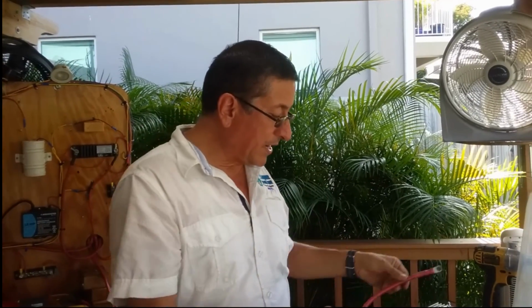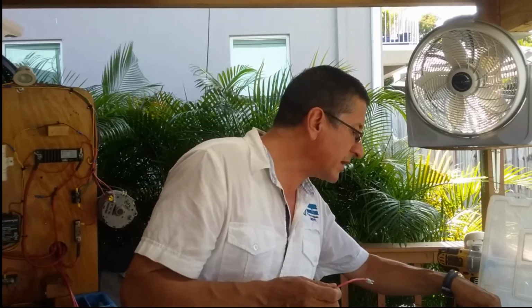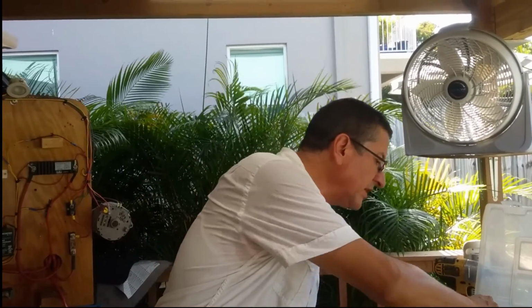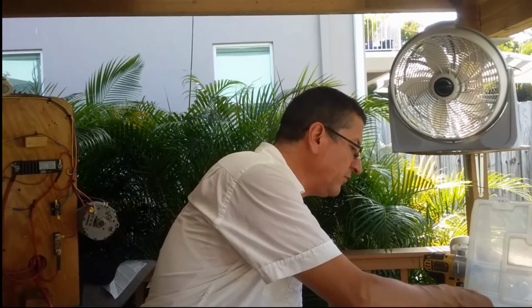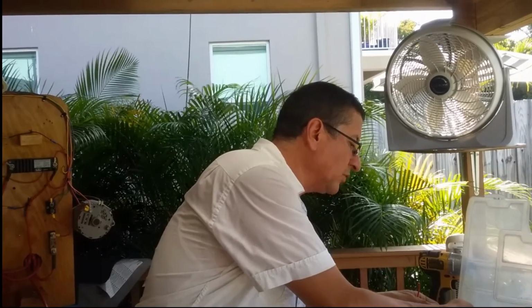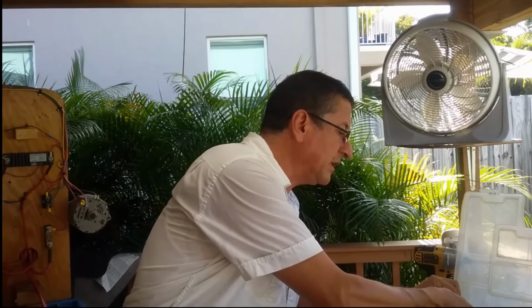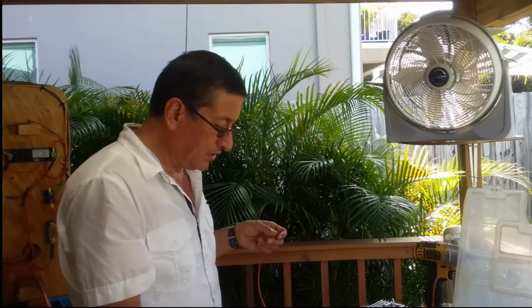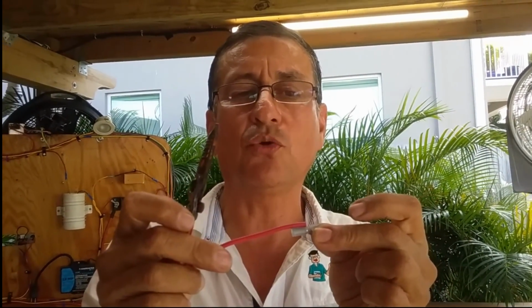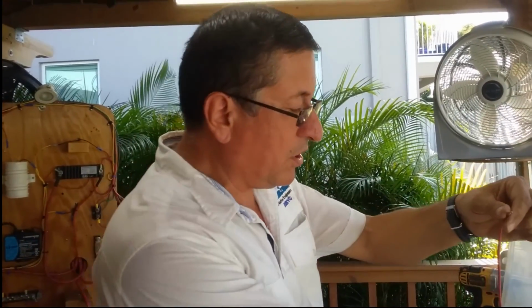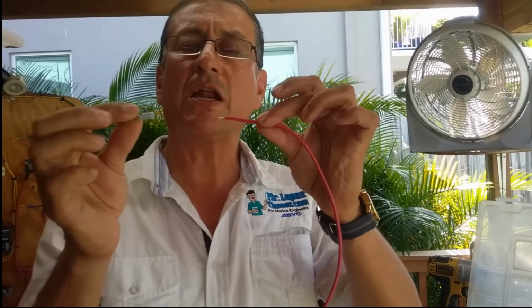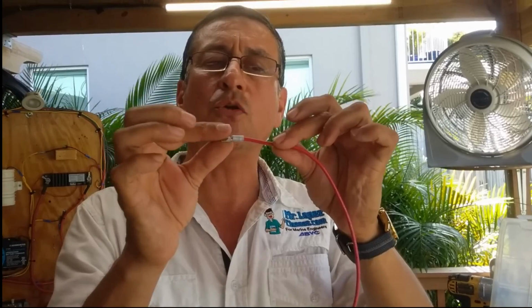Alright, I am going to prepare one cable and one wire, and install a terminal quickly on one of these cables. Let me show the procedure to crimp and install it. The first step is to verify how much insulation I need to remove according to the terminal. After that, you cut the insulation material, exactly the amount needed. Right now we are ready to introduce the wire into the terminal and crimp it.